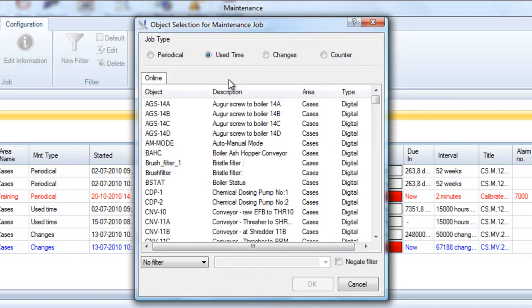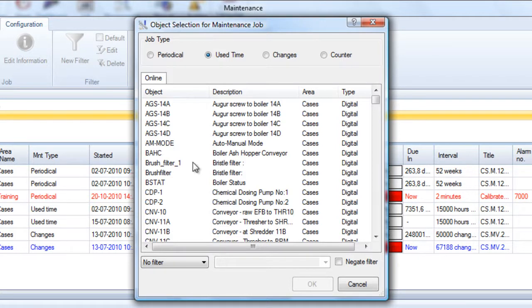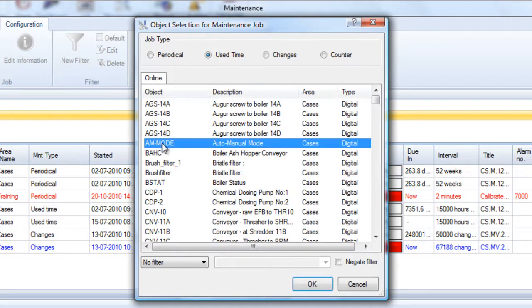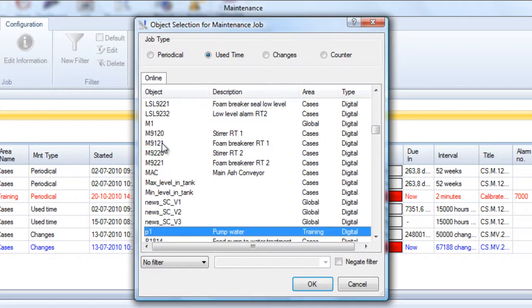Finally, we have counter maintenance which counts values and triggers when a specific counter is exceeded or a specific value of an analog object, then maintenance is due. Now let's choose a digital object for the use time maintenance. Let's choose P1 pump water, click OK, and we get a new use time job for P1.